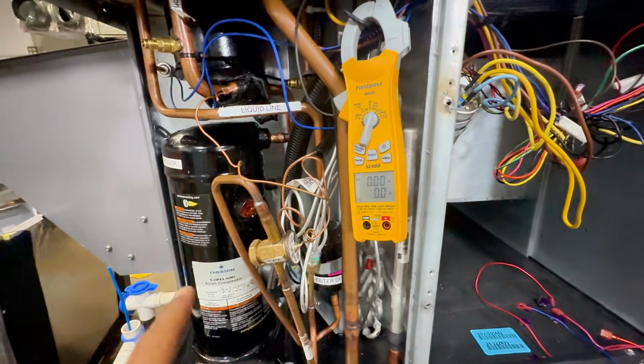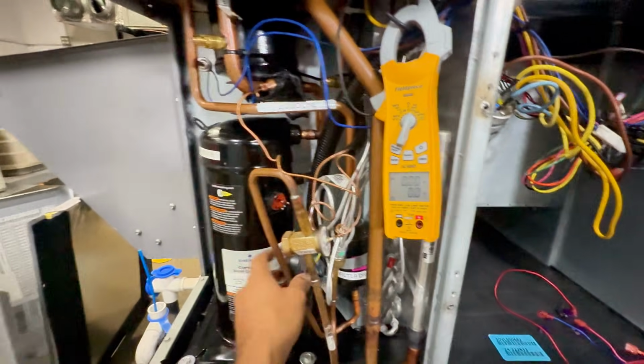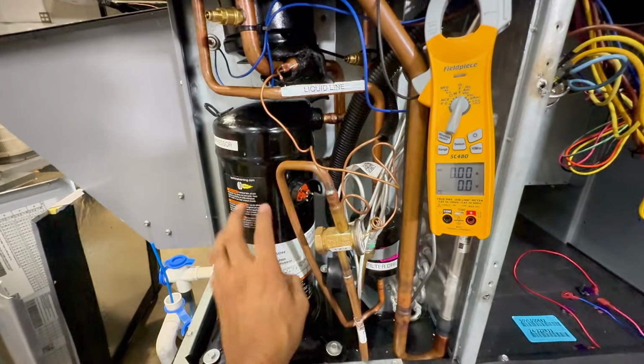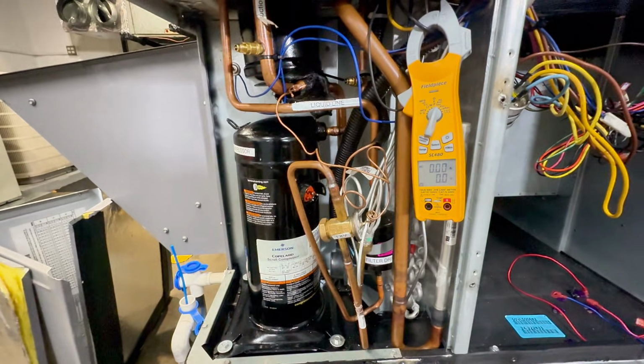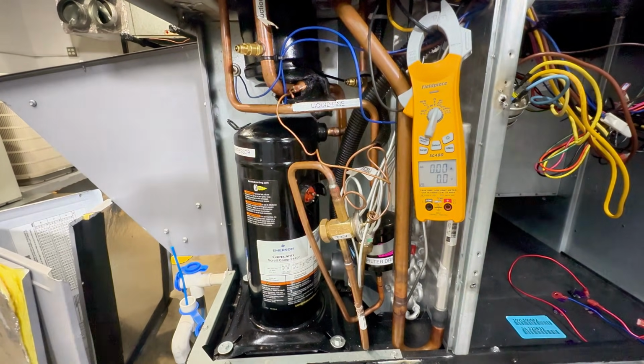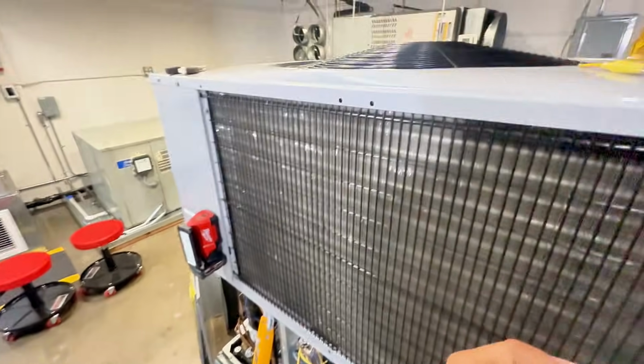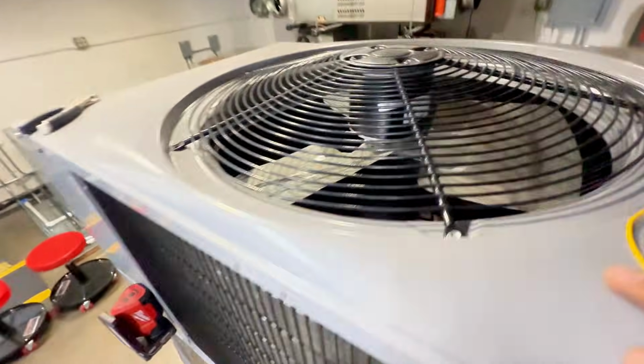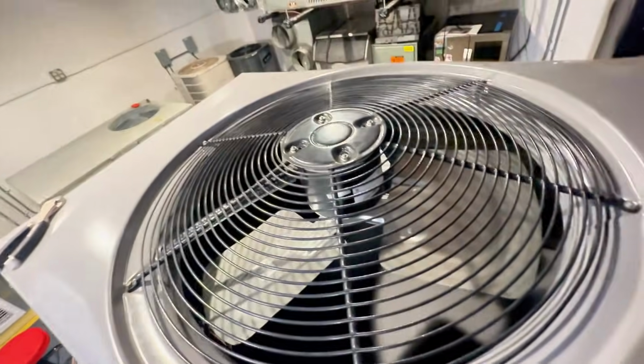So for this example, I did disconnect the plug. This is going to be for the compressor. This is going to be the one we're going to do next. But with this specific condenser fan motor, let's see if we're able to see it. You might not, and if not, that's okay. I can check it out for you. But let's see. Right there. Let's see what the full load amps is. Ooh, let's see. Oh, it's right there. Full load amps.